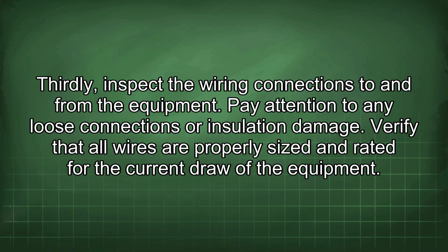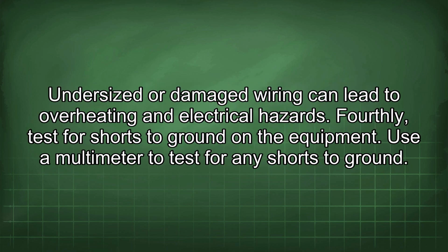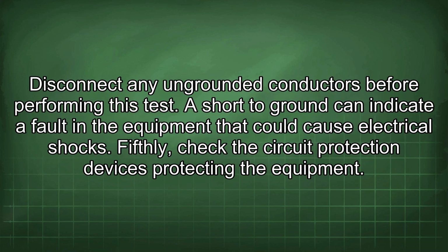Pay attention to any loose connections or insulation damage. Verify that all wires are properly sized and rated for the current draw of the equipment. Undersized or damaged wiring can lead to overheating and electrical hazards. Fourthly, test for shorts to ground on the equipment. Use a multimeter to test for any shorts to ground. Disconnect any ungrounded conductors before performing this test. A short to ground can indicate a fault in the equipment that could cause electrical shocks.